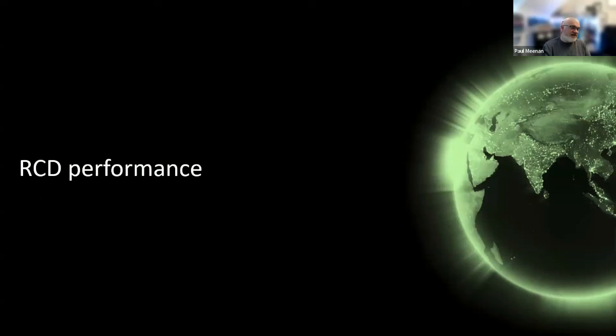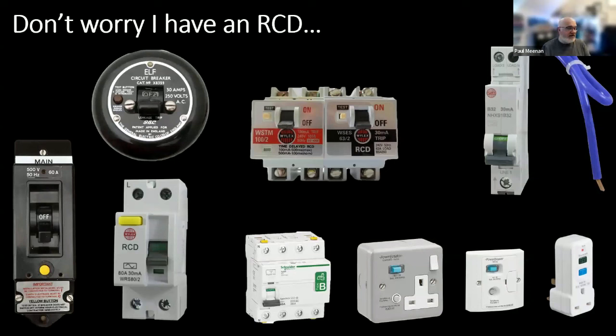So, just on to one of the last bits, RCD performance. RCDs are a wonderful bit of tech. They've been out for many, many years, since 1939. Some of the examples were voltage earth leakage circuit breakers, VOELCBs, RCDs to BS 4293, BS EN 61008, and BS EN 61009. So we've gone on a huge journey of making the earth leakage protective device accessible to the market, and all it's ever done is improve safety. It protects against fire and it protects against indirect shock. So it's a good thing if it works. And Krish's excellent webinar raised a few points on the correct selection, erection and configuration of RCDs, because some of these do rely on a functional earth connection.